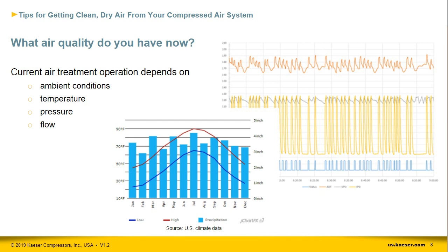Keep in mind, it's always good to monitor system operation, temperatures, and pressures. If you're getting water downstream, check the operating conditions in the compressor room and also at the point of use, and that can help you figure out how to solve the problem.